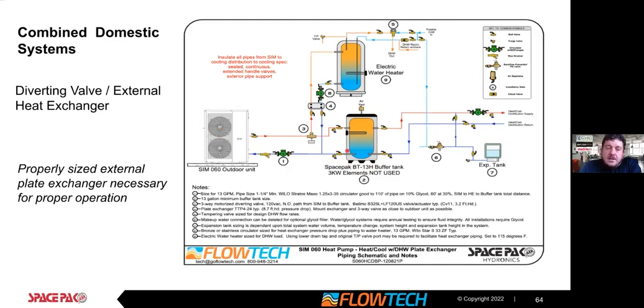And when it gets a domestic call in this application, and there's variations of a theme on this. If you're in our territory, please reach out to us, because we've taken leadership on the DHW integration, and you can see this is an approved design that we've put together to help contractors and engineers put this together. SpacePak operates this diverting valve, and it feeds the external flat plate heat exchanger and feeds an electric water heater with a backup element. I think the two top takeaways here is, number one, backup is critical on these, with the element and the water heater to hold the floor up and provide backup heating.